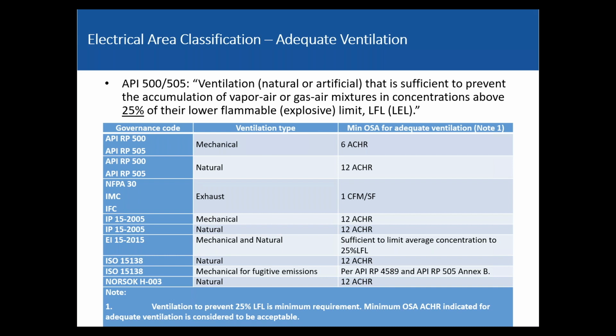Luckily, there are two different ways you look at this. One is that each of the governing codes gives us a nice prescriptive amount. So that's really cool. Looking at API RP 500, for mechanical ventilation we have to use 6 air changes an hour. We've got IMC, 1 CFM per square foot, and another one is 12 air changes an hour. For natural ventilation, what's causing it? There are a couple of different ways you look at it: temperature-induced ventilation, and ambient wind.